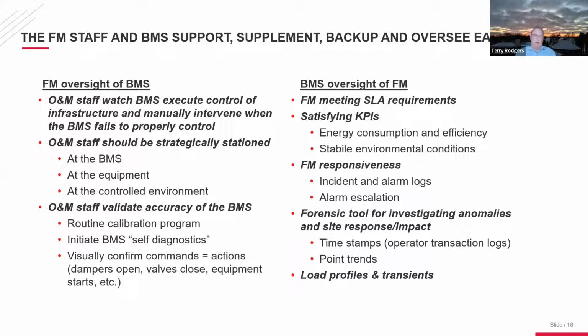On the flip side, the BMS is providing some oversight of your facility management staff. It can ensure they're meeting service level agreement requirements. For instance, if it's a data center and you're required to provide ASHRAE recommended conditions at the inlet in the computer cold room, cold aisles, then the BMS can be used to monitor that over time and trend it, and then you can go back and prove that you were meeting your SLA. It can be used to track other key performance indicators like energy consumption and stable environmental conditions, et cetera.